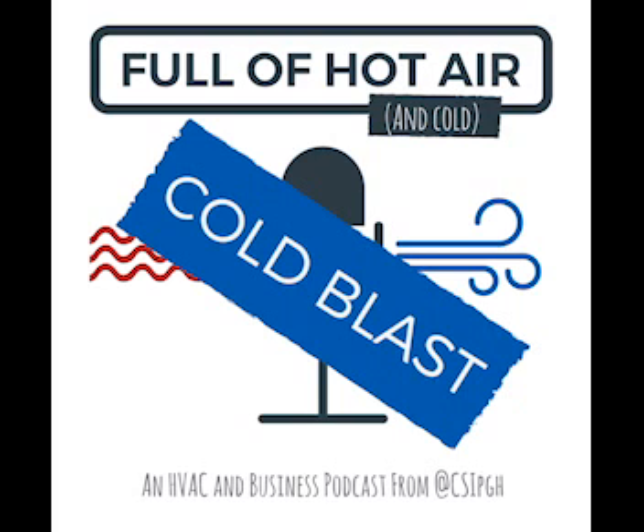Gotcha. So it's kind of cool. Does that pose a unique situation for guys that aren't used to the Mitsubishi product? Is that something unique to Mitsubishi? It is different because they're usually looking for high voltage. They really don't know which wires are high voltage and which wires are low voltage. So I'll get a lot of guys calling and giving me readings, and they're on the wrong scale on their meter to be checking the voltage.